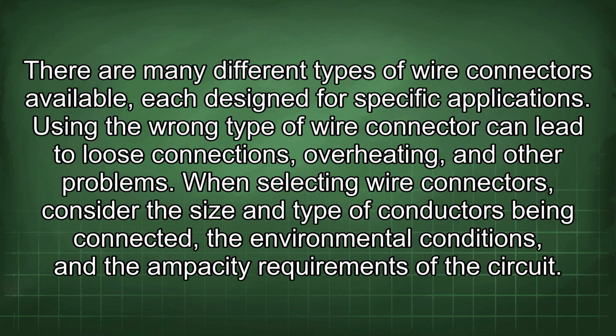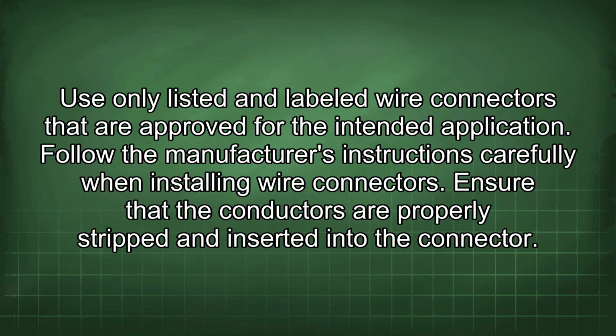There are many different types of wire connectors available, each designed for specific applications. Using the wrong type of wire connector can lead to loose connections, overheating, and other problems. When selecting wire connectors, consider the size and type of conductors being connected, the environmental conditions, and the ampacity requirements of the circuit. Use only listed and labeled wire connectors that are approved for the intended application.